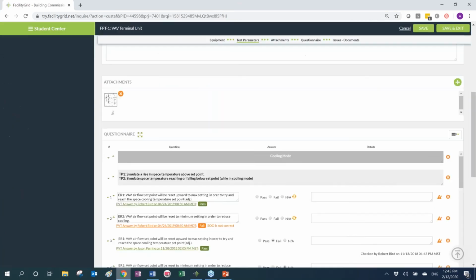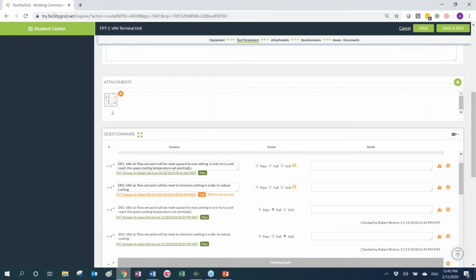The responses the contractor provides as part of pre-verification testing are embedded into the functional testing. You can see right here, I'm looking at the FPT, and this FPT has the answers from the contractor embedded directly into the test form. For this particular question, the contractor's answer was that this sequence of operation is not correct—they pre-tested it and that sequence doesn't work.